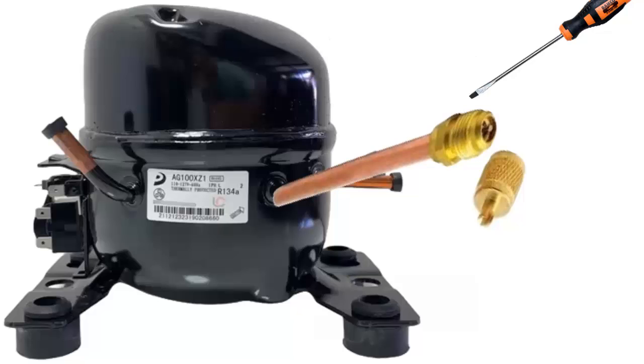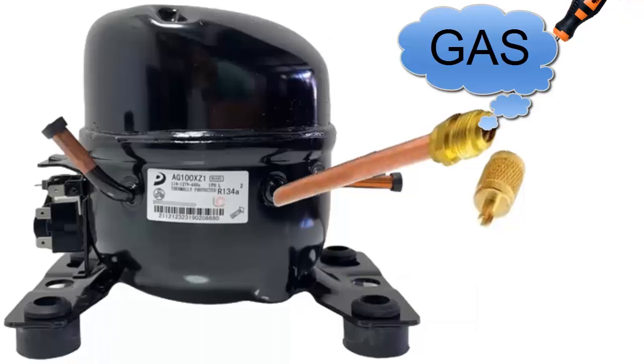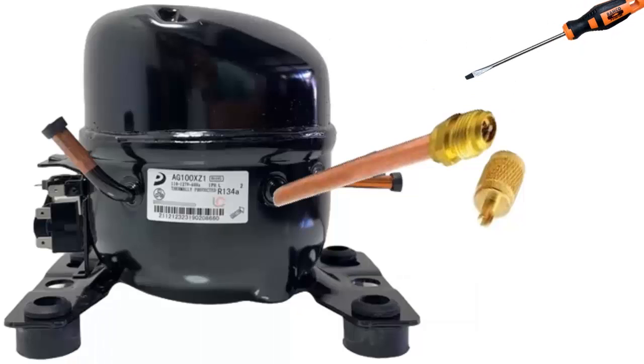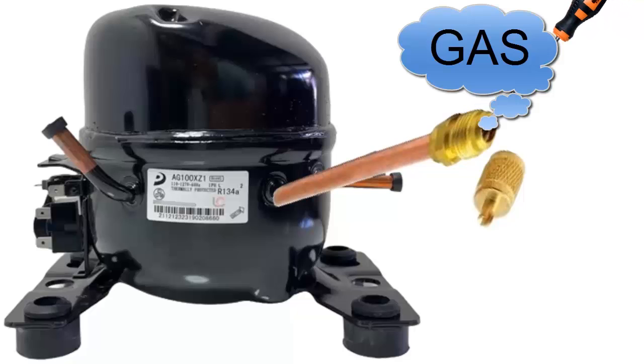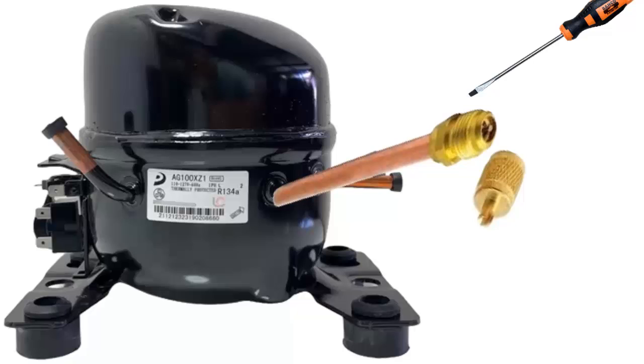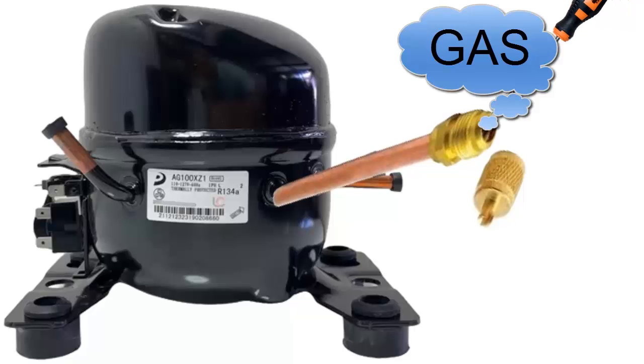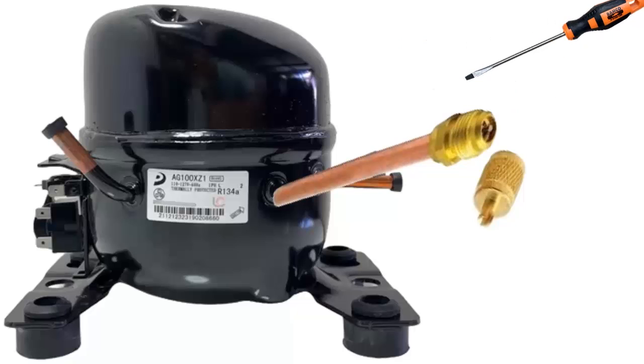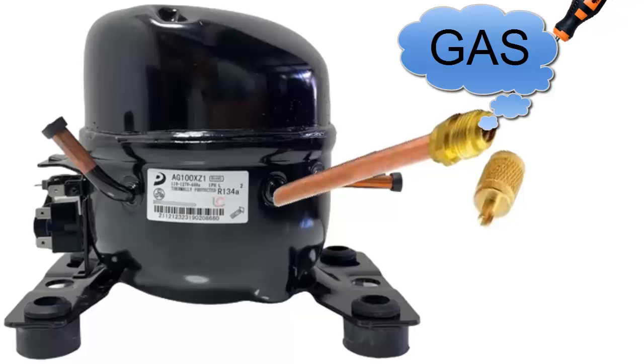Method 9: If the compressor has a service port, with the equipment off, use a screwdriver to pierce the gas port. If refrigerant gas comes out, the equipment still has a charge. This last test only indicates if there is gas present, not the quantity.